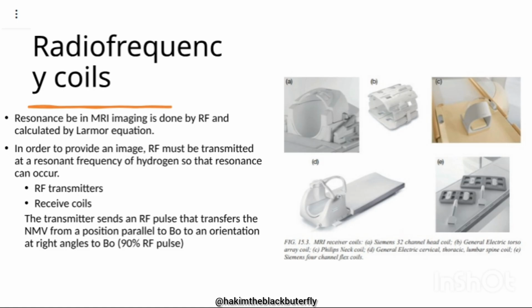Resonance in MRI imaging is done by RF and calculated by the Larmor equation. In order to provide an image, the RF must be transmitted at the resonant frequency of the hydrogen, and that resonant frequency is what we call the Larmor frequency. So the radio frequency should move at a frequency equal to the frequency at which the hydrogen nuclei are spinning, and that's when we shall have resonance. And when we don't have resonance taking place, we can never have the MRI signal induced.